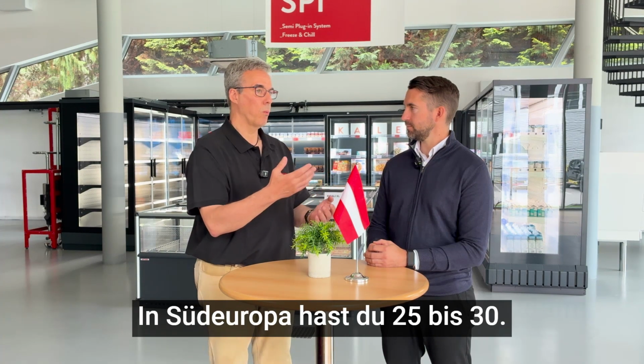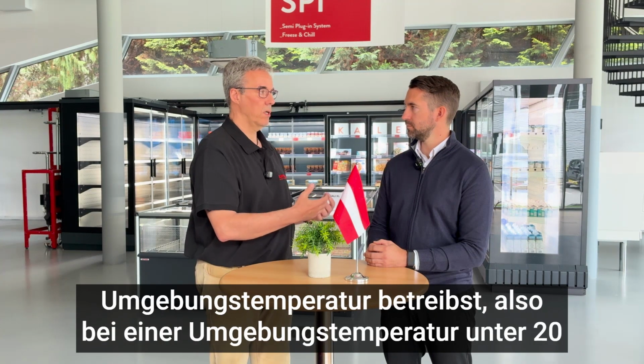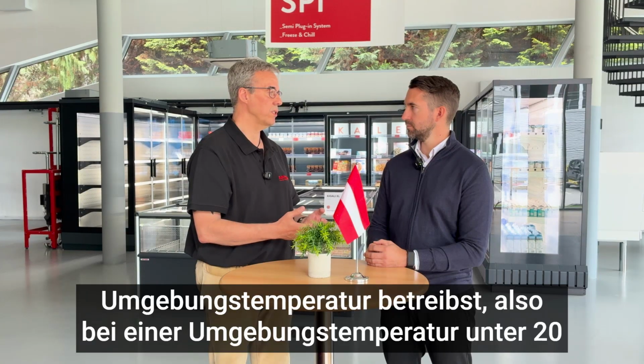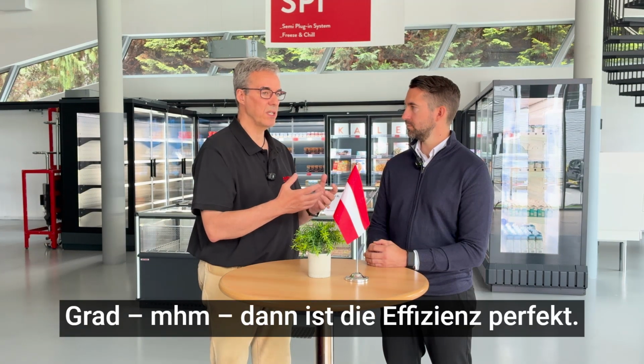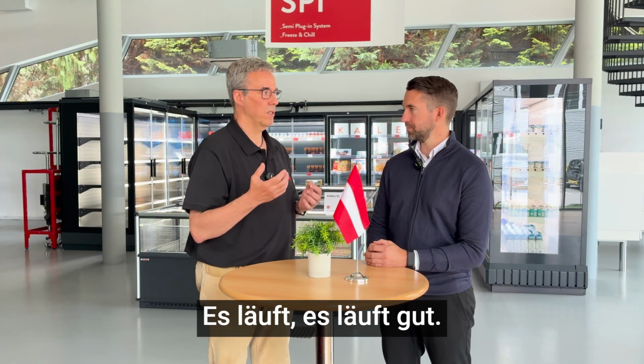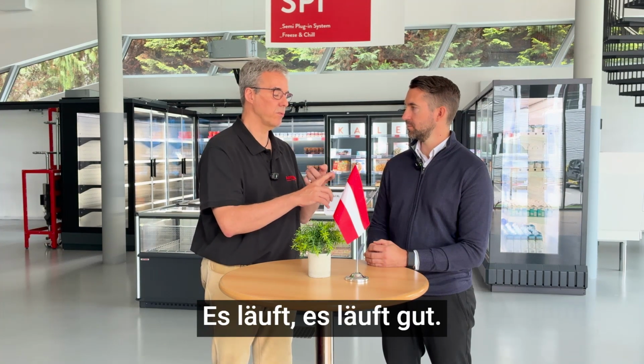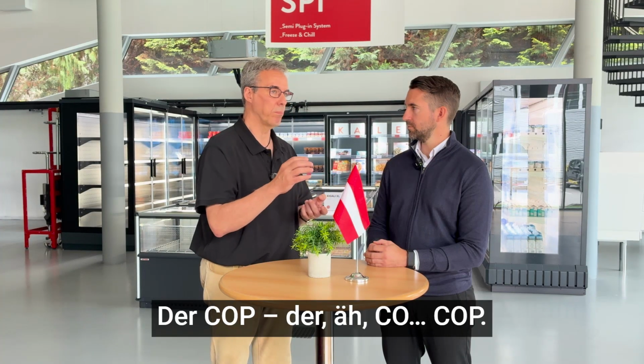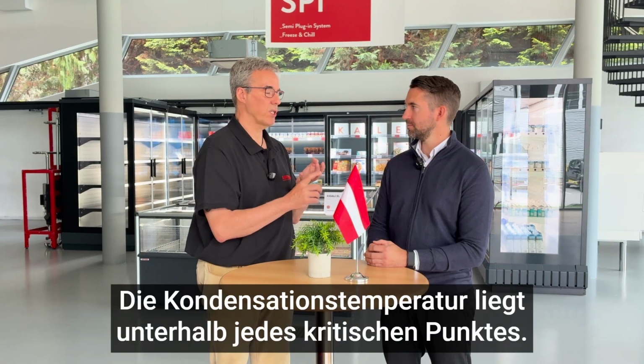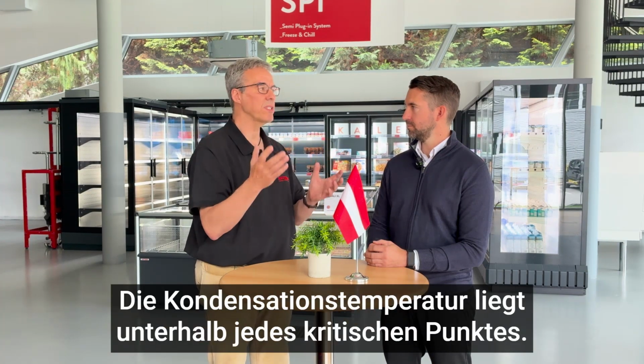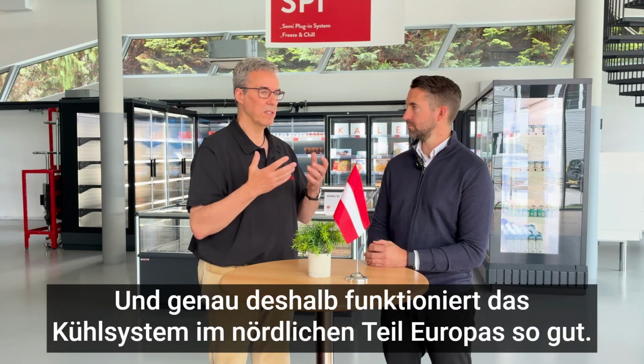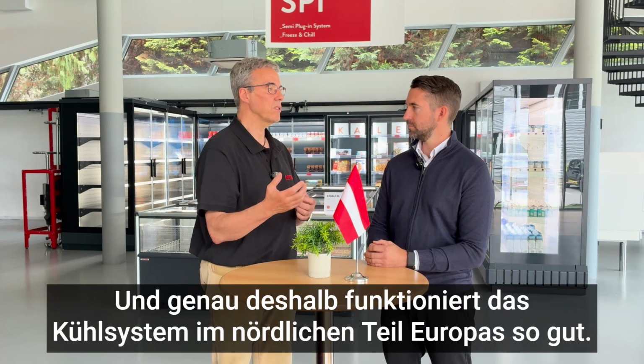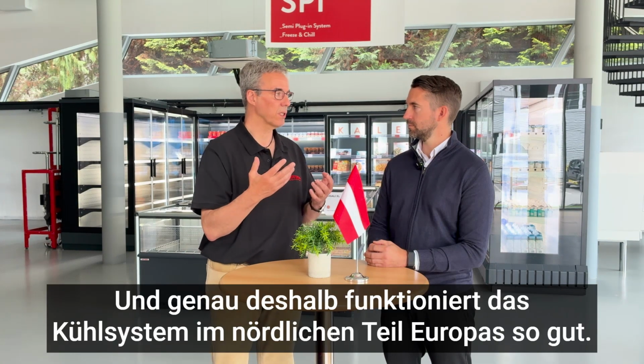Okay. So when you work your CO2 system or any cooling system with a low ambient temperature, lower than 20 degrees, then you have perfect efficiency. It's running well. The COP, the compressor is running perfectly. The condensing temperature is below the critical point. And that's the point why the cooling system in the northern part of Europe is working well.